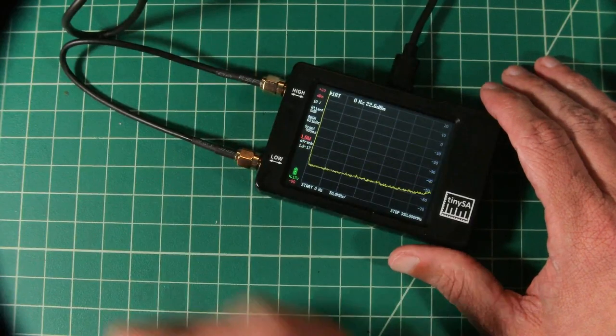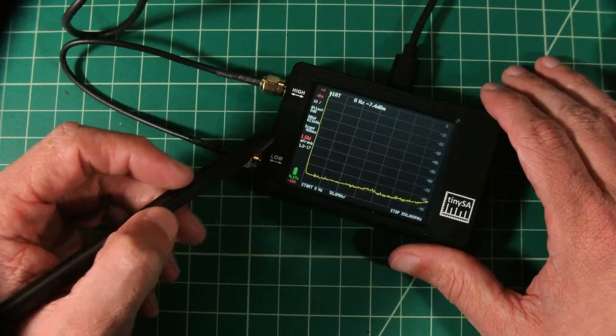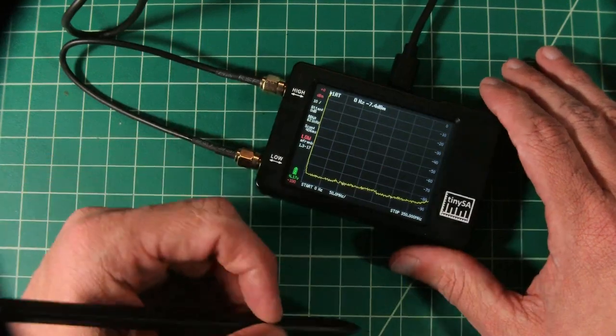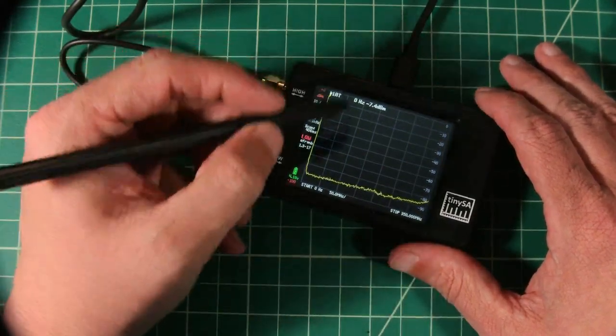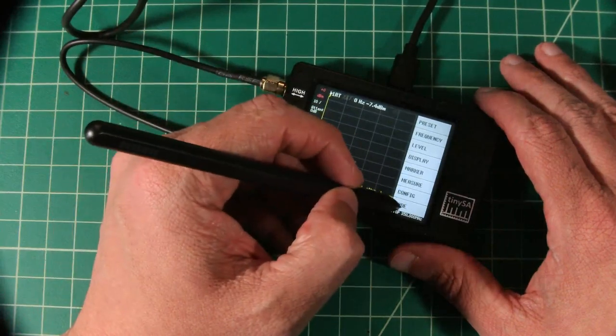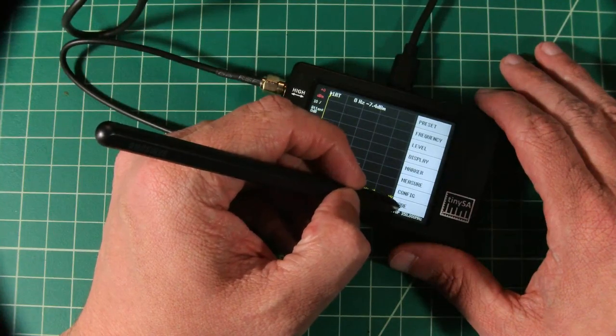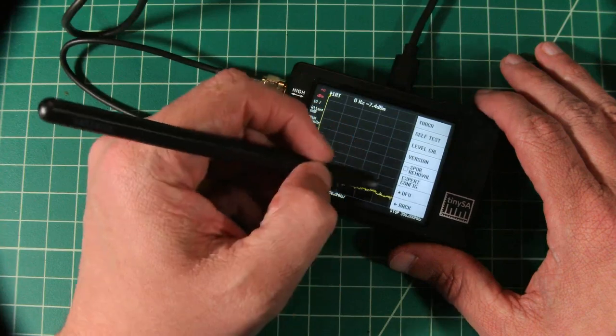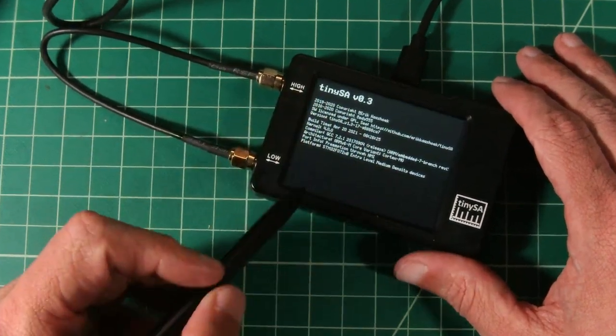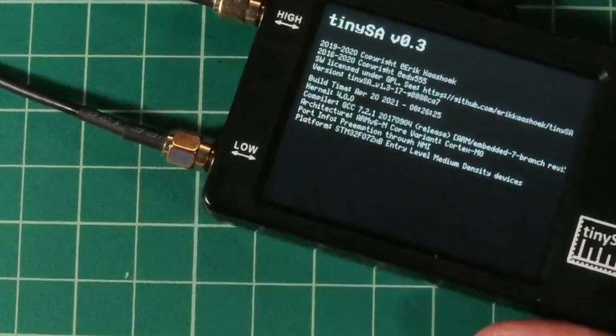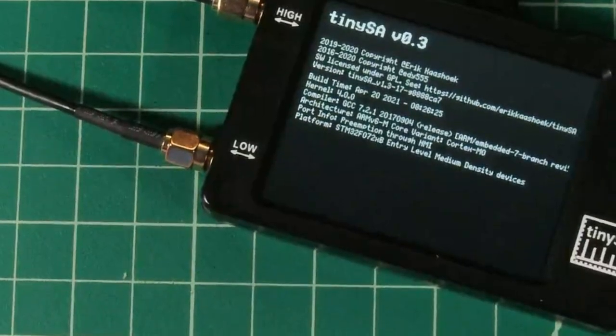And it boots up and as you can see these are in red because we need to go back and do our level set and our calibration again. Anyhow, let's just go ahead and open up the menu and I am going to go to config and then go to version. And then here you can see the new version number is 1.3-17 and it looks like our update was successful.